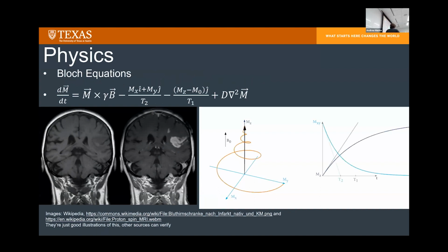In an MRI image, you have a collection of proton spins inside a large magnetic field, which provides a Z direction field. Then you use an RF pulse to knock them into the XY plane, and you measure their decay back up towards the Z field. While they're decaying, they can also spread out from each other. The spreading out causes a decay in your XY magnetization that is characterized by a decay time T2. The return to the Z direction magnetization is characterized by a decay time T1.